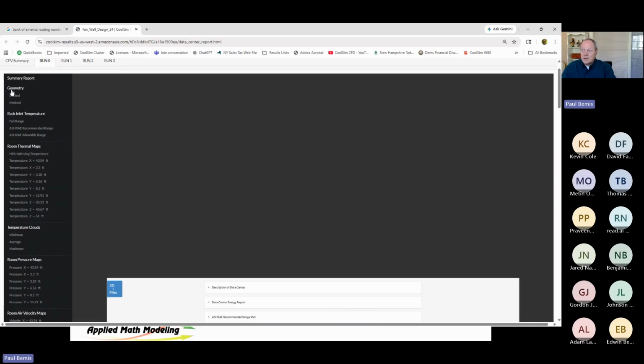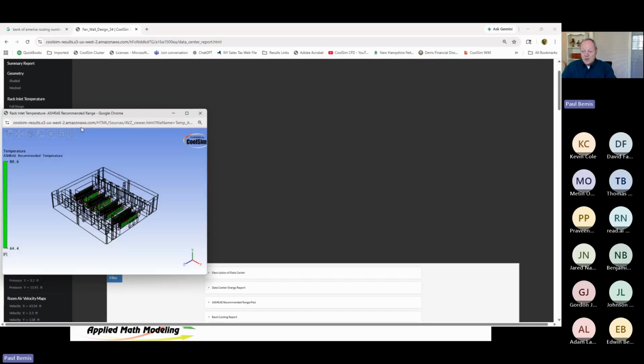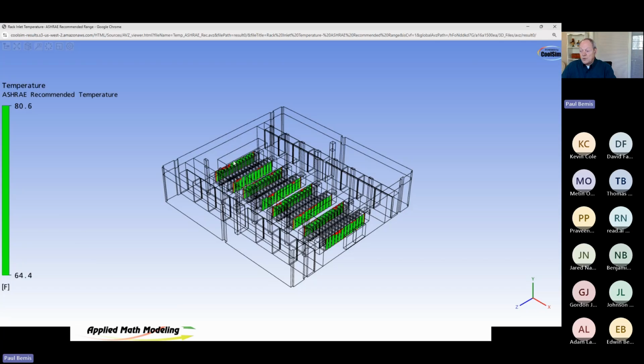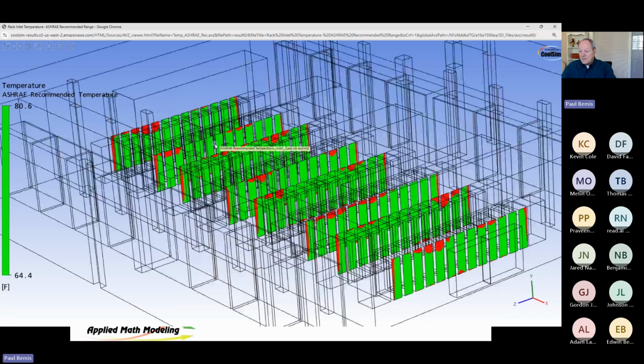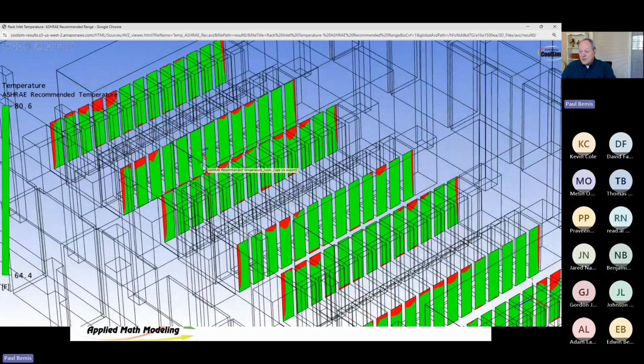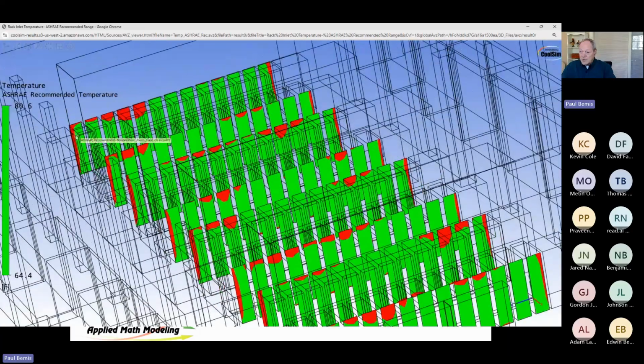So let's go look at it graphically. The most important one is ASHRAE recommended range. This is really the go, no go kind of gauge, if you remember that. And you see that my racks are having some issues. Not all of them, but some of them. And guess where? On edges.